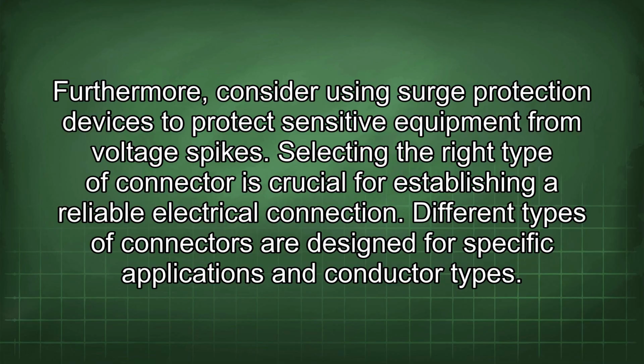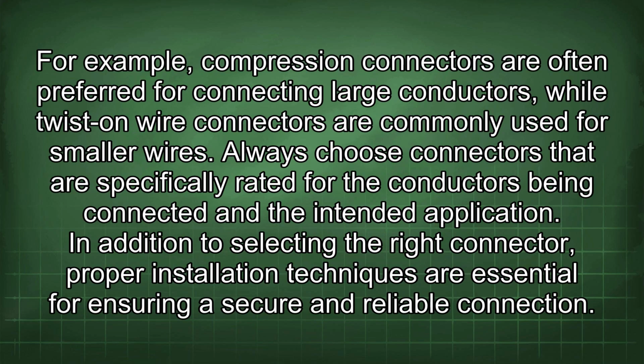Selecting the right type of connector is crucial for establishing a reliable electrical connection. Different types of connectors are designed for specific applications and conductor types. For example, compression connectors are often preferred for connecting large conductors, while twist-on wire connectors are commonly used for smaller wires. Always choose connectors that are specifically rated for the conductors being connected and the intended application.